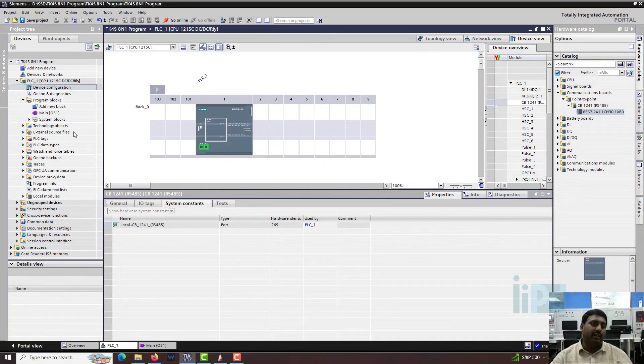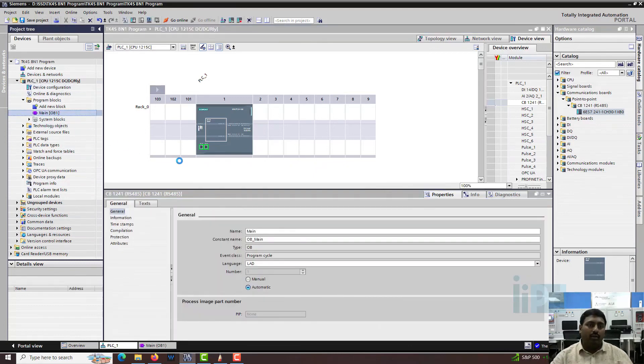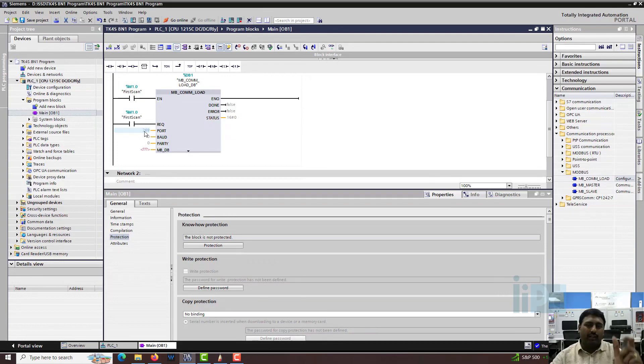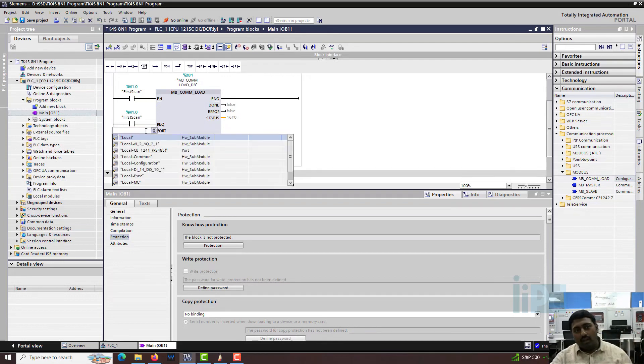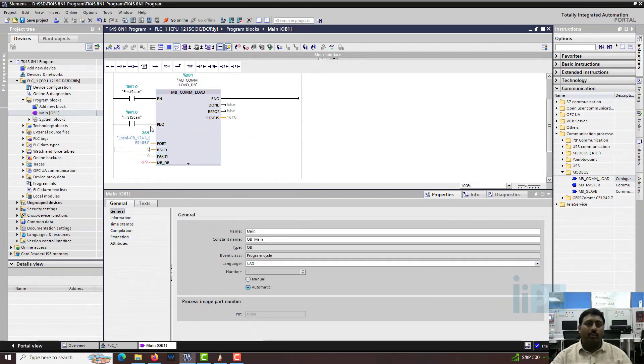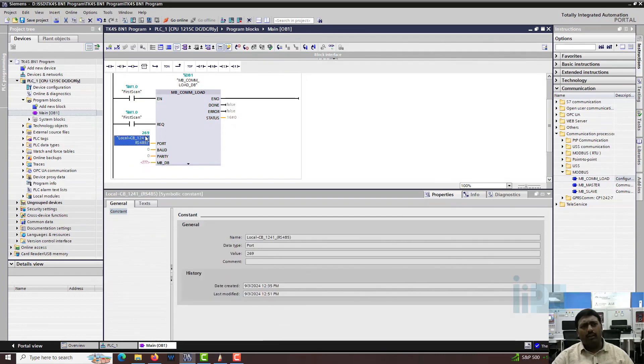This port number is the hardware identifier. If you go to the main block and directly type 269, it will take it but may not show the correct symbolic value. Instead, click the three-line dropdown, select local CB1241 port RS-485, and it will automatically populate 269. You can enter 269 directly as well, but the dropdown shows the exact port address.